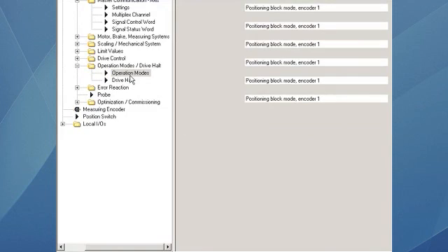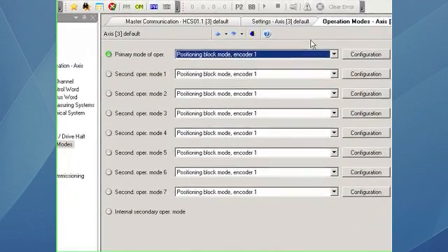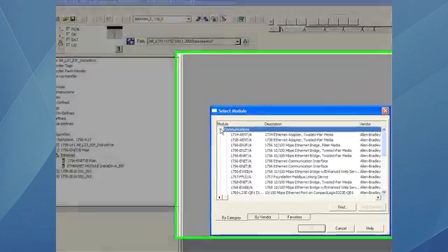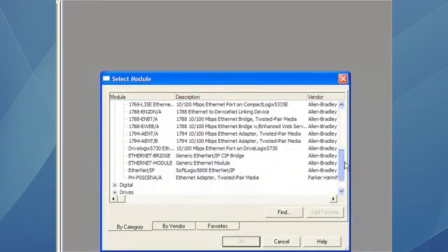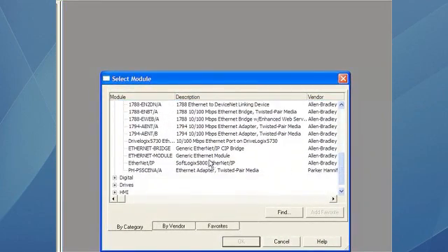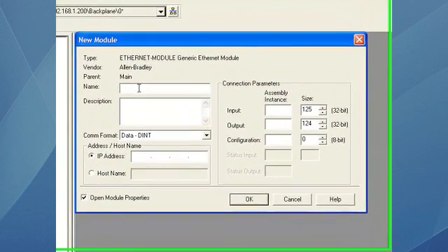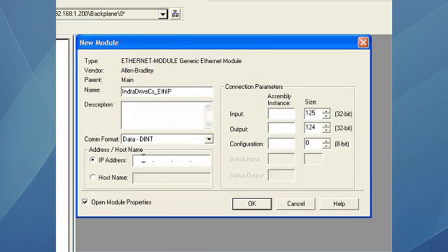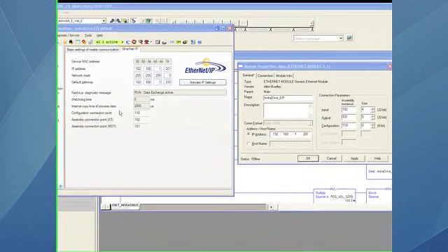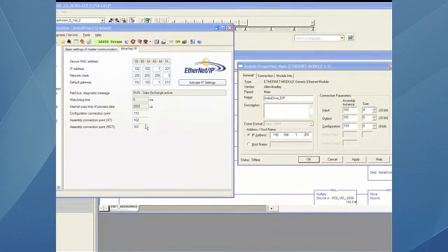Now we have to go back to the PLC. In the PLC, we have to insert an Ethernet module. We go to the communication trees and select Ethernet module, generic Ethernet module. And here we will set up what we configured for the drive. We will set up the IP address, the assembly instance input and output, the configuration number, and the size.